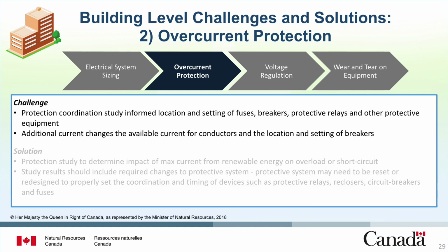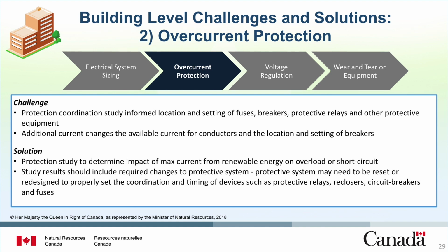The good news is there are solutions to this challenge. New studies may be required in order to determine how the maximum current from a renewable energy generator increases currents flowing through the electrical system when a line becomes overloaded or when a fault, such as a short circuit, occurs. Results of this study should include any required changes to the protective system used to detect and interrupt current and isolate faults. The protective system may need to be reset or redesigned to properly set the coordination and timing of devices, such as protective relays, reclosers, circuit breakers, and fuses in a system to detect and isolate faults.